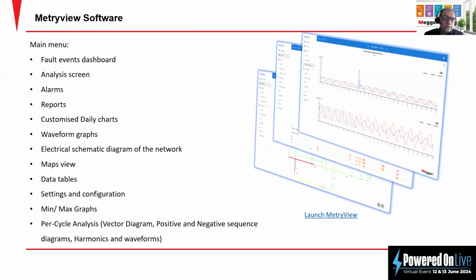The main menus give lots of information, like the fault events dashboard, analysis screen, alarms, reports, customized daily charts, daily, weekly, yearly, waveform graphs, electric schematic diagram of the networks, map view, data tables with all the information, setting and configuration, min and max graphs, Per-Cycle Analysis, including vector diagram, positive, negative and zero sequence, harmonic and waveforms.